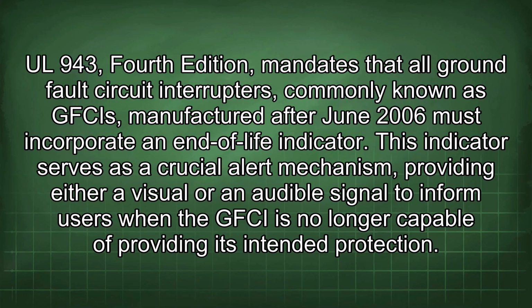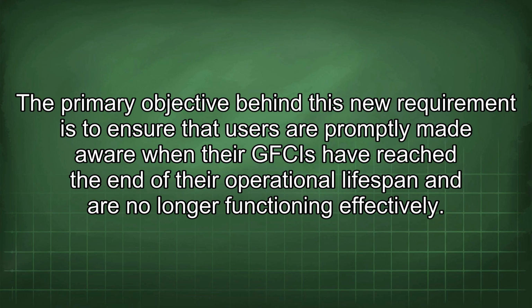UL 943 4th edition mandates that all ground fault circuit interrupters, commonly known as GFCIs, manufactured after June 2006 must incorporate an end-of-life indicator. This indicator serves as a crucial alert mechanism, providing either a visual or an audible signal to inform users when the GFCI is no longer capable of providing its intended protection. The primary objective behind this new requirement is to ensure that users are promptly made aware when their GFCIs have reached the end of their operational lifespan and are no longer functioning effectively.